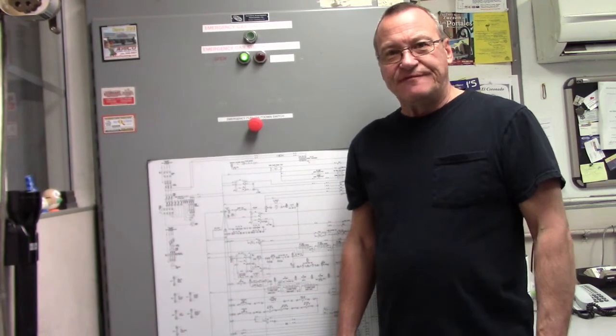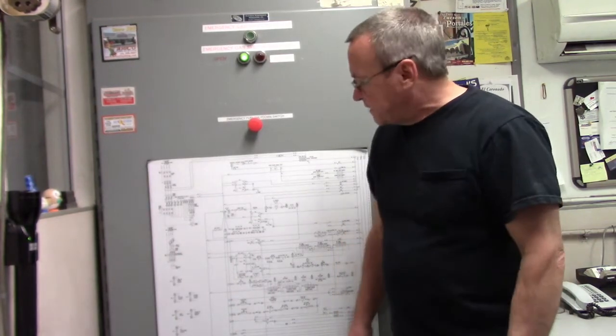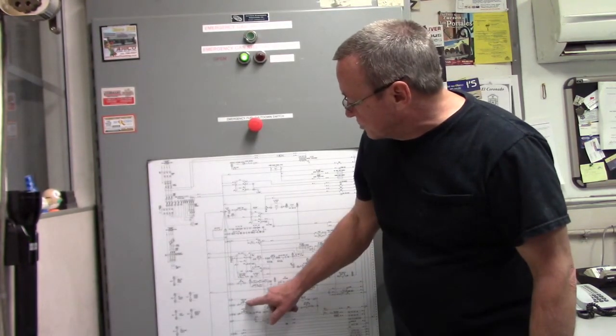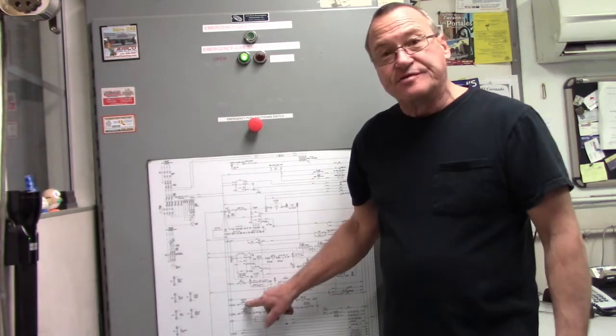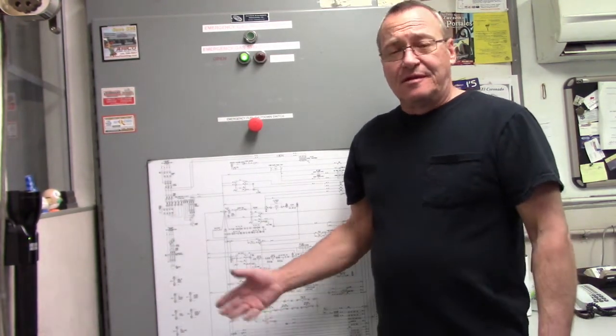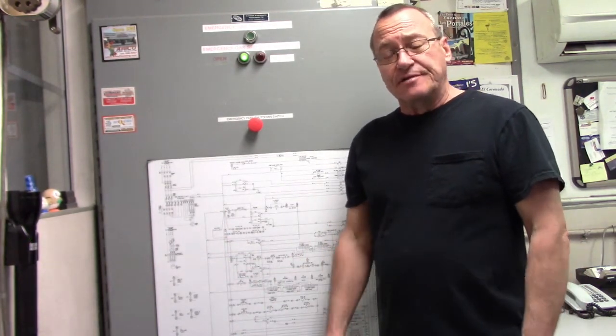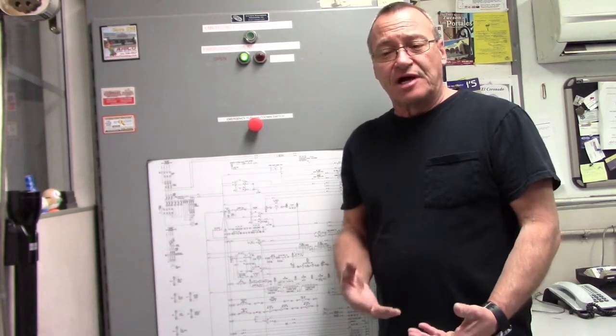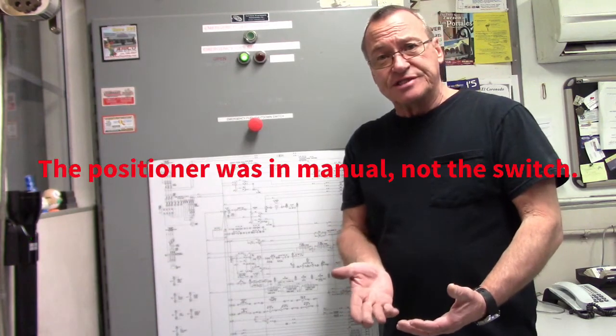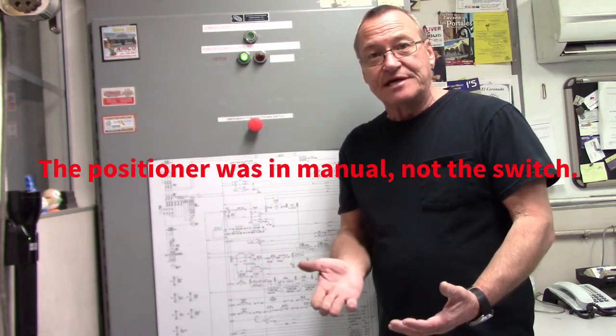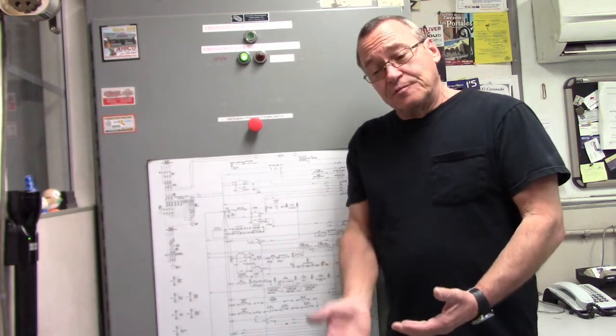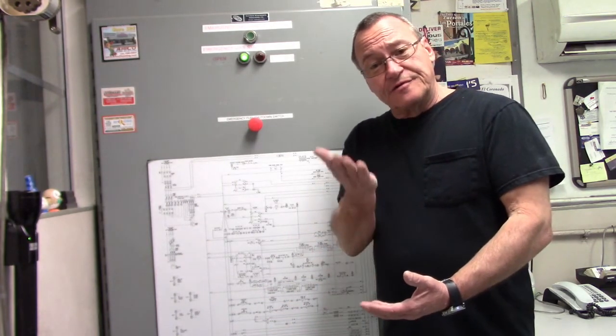So in that situation we found that the inlet damper, or what's called louver motor purge proving switch on the diagram, didn't open initially and was preventing the boiler from going into purge. I found the problem: it was in manual. The positioner itself was in manual. When I had done maintenance I left it in manual; I forgot to put it in auto.